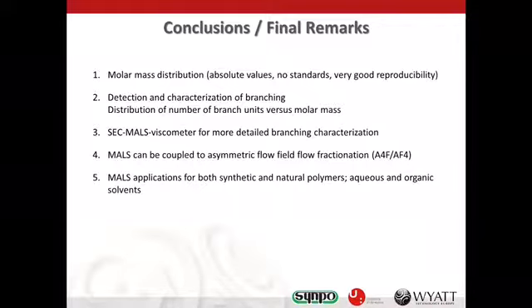The next question: How is it possible to calculate the very exact molecular mass of a protein independent of its shape? Actually, the molar mass is always measured independently of shape — that is an advantage of light scattering. Looking at the basic light scattering equation, there are no shape-related parameters. The molar mass is measured only from the intensity of scattered light at zero angle and from the concentration, so shape does not matter.